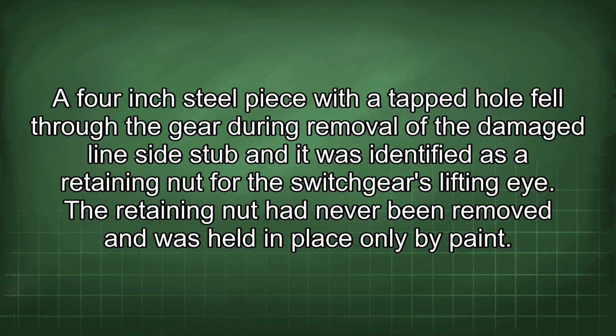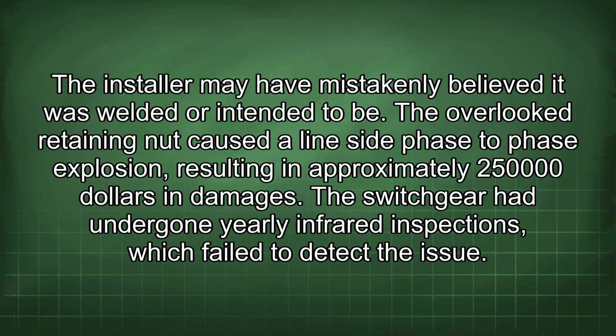A 4-inch steel piece with a tapped hole fell through the gear during removal of the damaged line side stub, and it was identified as a retaining nut for the switchgear's lifting eye. The retaining nut had never been removed and was held in place only by paint. The installer may have mistakenly believed it was welded or intended to be.